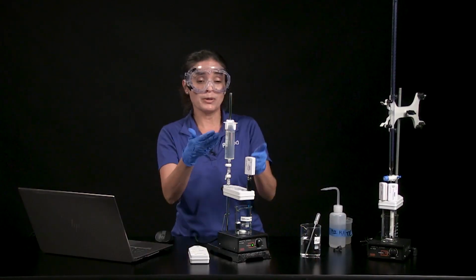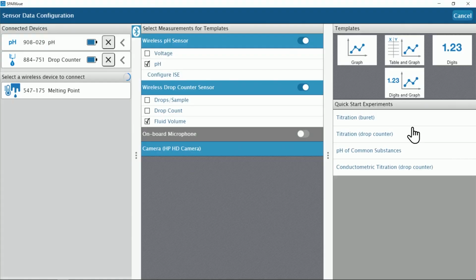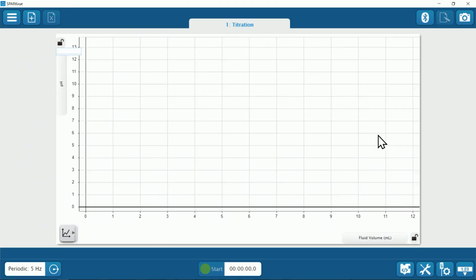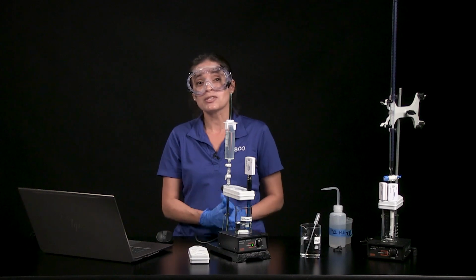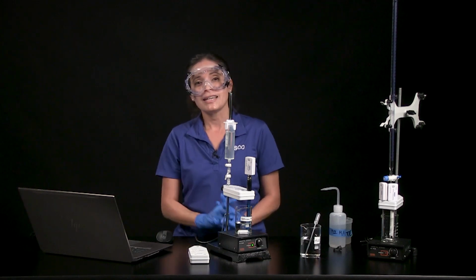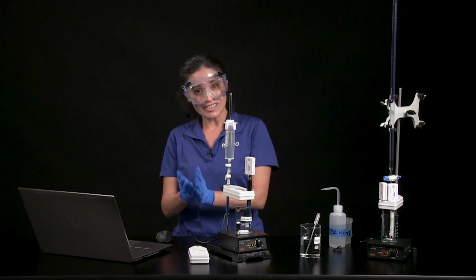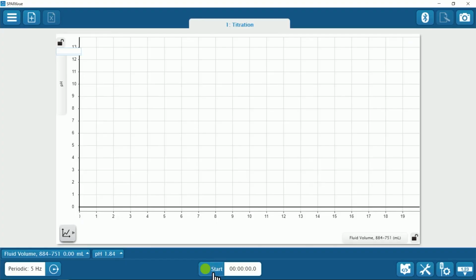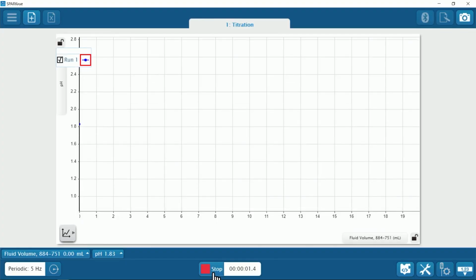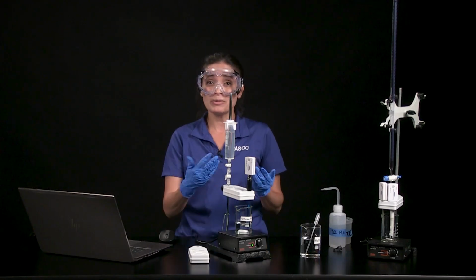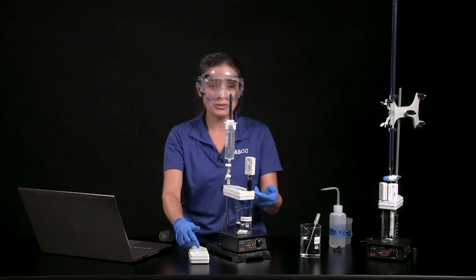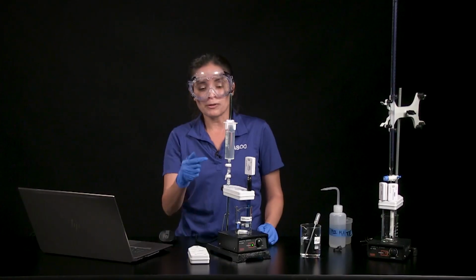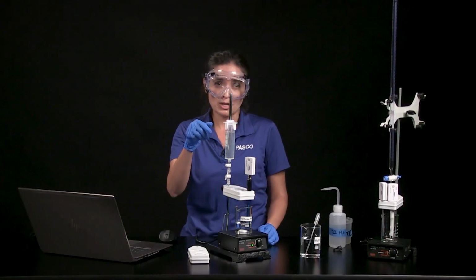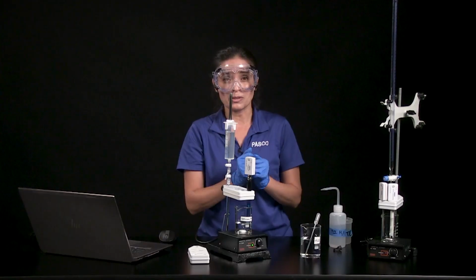I've already connected both of these sensors in SPARKvue, and I'm going to choose the pre-built titration drop counter experiment. The drop counter is also compatible with Capstone and Chemvue software. Now that the setup is complete, let's start collecting titration data. I'm not rushing here because the volume data will only be recorded while drops are falling through the counter window. Once I fully open the top valve to let the drops through, the pH and volume data are recorded on the graph.